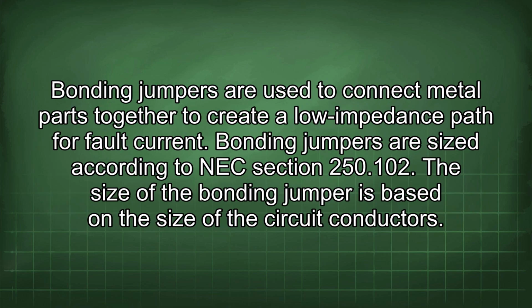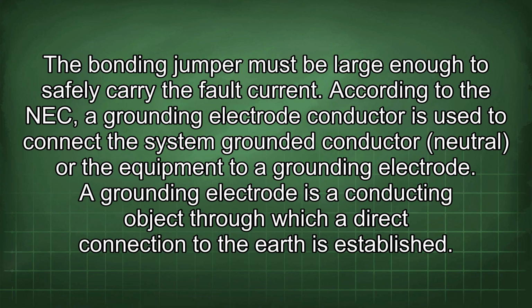Bonding jumpers are used to connect metal parts together to create a low impedance path for fault current. Bonding jumpers are sized according to NEC Section 250.102. The size of the bonding jumper is based on the size of the circuit conductors. The bonding jumper must be large enough to safely carry the fault current.